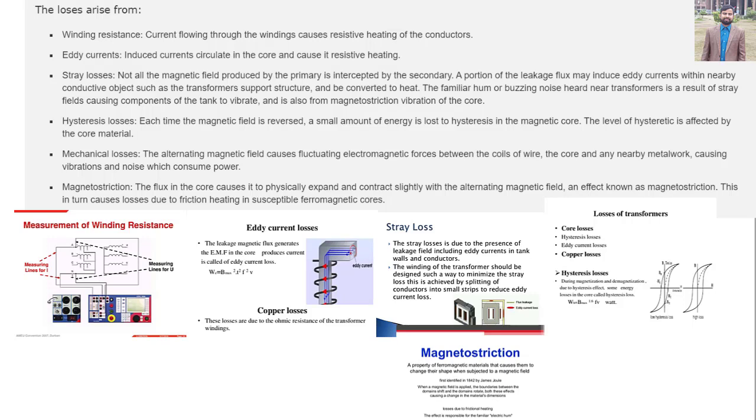the alternating magnetic field causes fluctuating electromagnetic forces between the coils of wire, the core, and any nearby metalwork causing vibrations and noise which consume power. Magnetostriction: the flux in the core causes it to physically expand and contract slightly with the alternating magnetic field, an effect known as magnetostriction. This in turn causes losses due to friction heating in susceptible ferromagnetic cores.